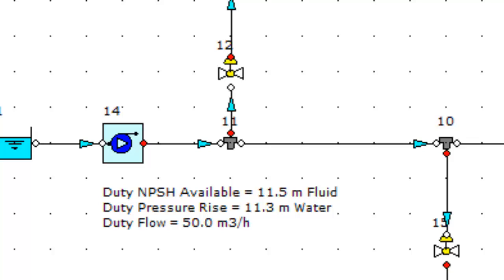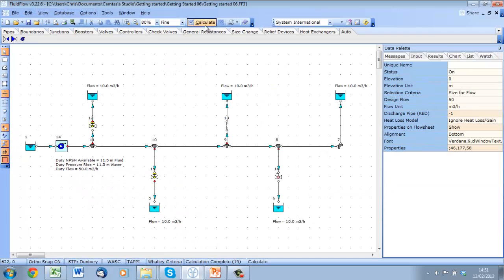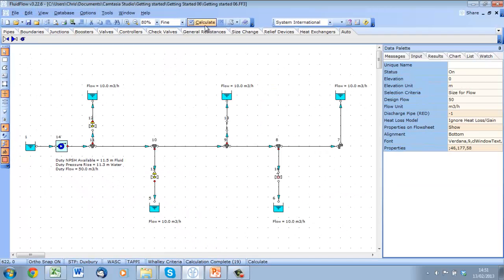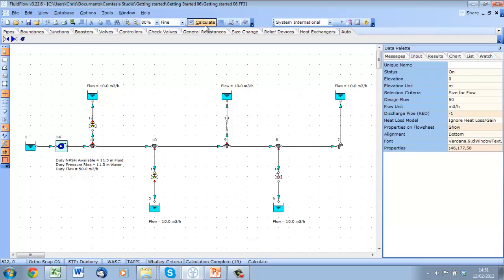It is more likely that when designing a system, a duty range will be supplied. This can be investigated in Fluid Flow 3 by simply changing the set point of the auto booster to generate a duty point at the maximum, minimum, and operating flow conditions.